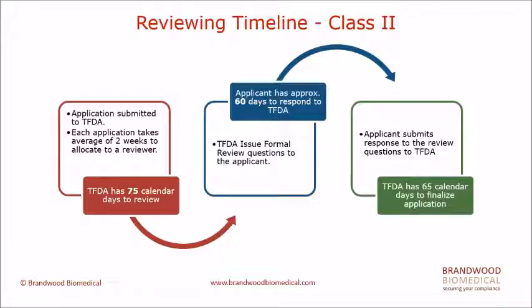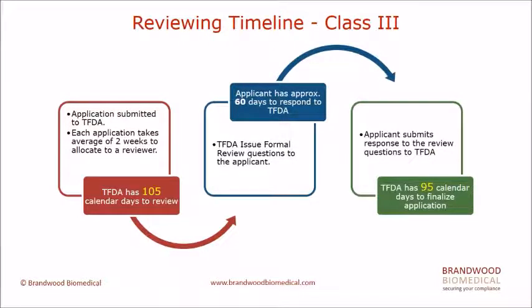decision to the manufacturer. For Class 3 devices, the reviewing process is pretty much the same as the Class 2 device applications. The only difference is the reviewing timeline. The initial feedback the manufacturer or the sponsor should hear back from Taiwan FDA is around 105 calendar days, roughly about 3.5 to 4 months.